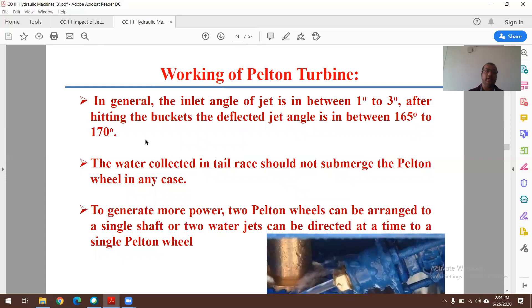The inlet angle of the jet is between 1° and 3°. After hitting the buckets, the deflected jet angle is between 165° and 170°. Water collected in the tailrace should not submerge the Pelton wheel under any circumstances. To generate more power, two Pelton wheels can be arranged on a single shaft, or two water jets can be directed onto a single Pelton wheel — both approaches enhance efficiency and power output.